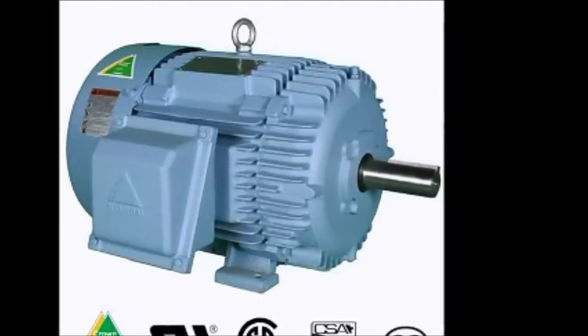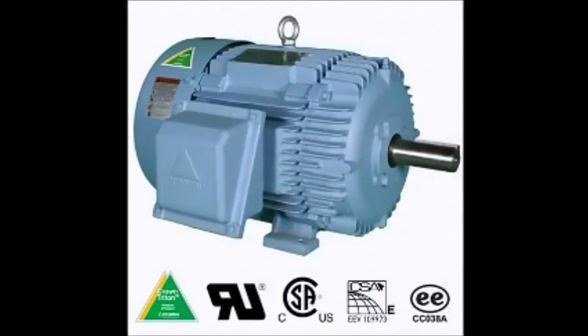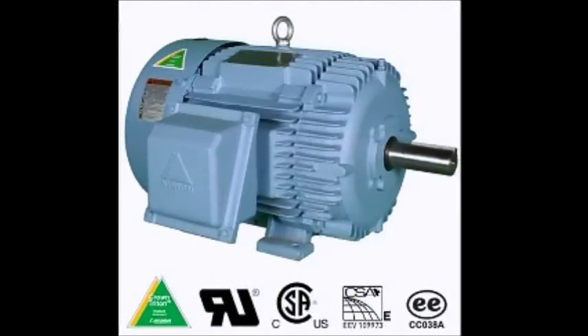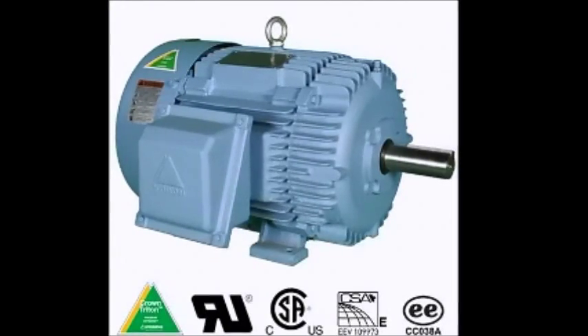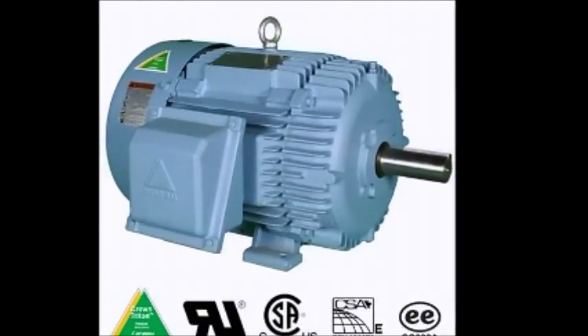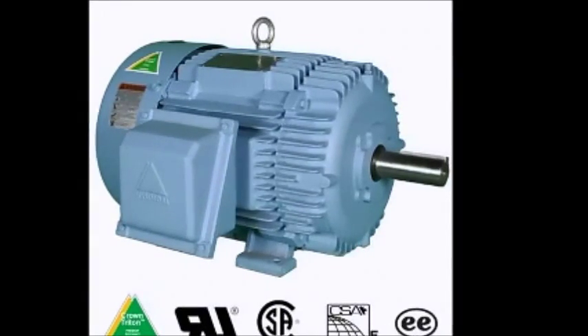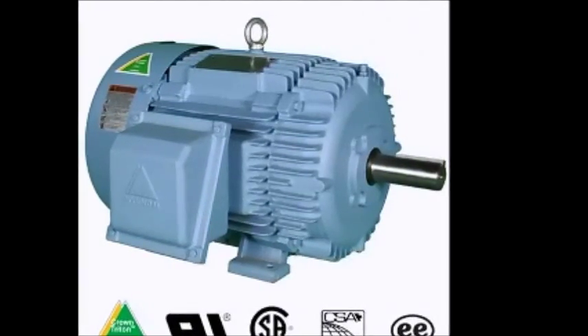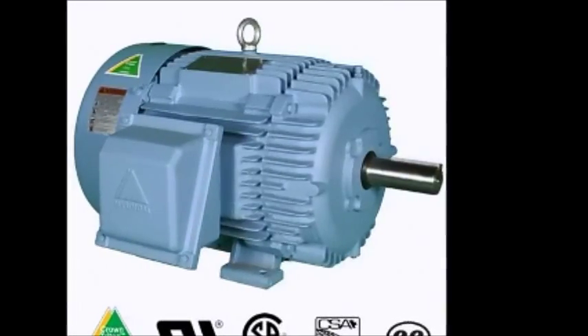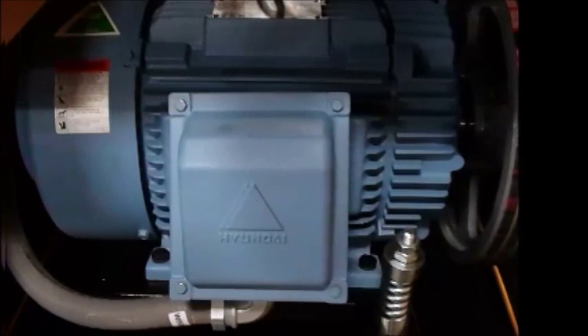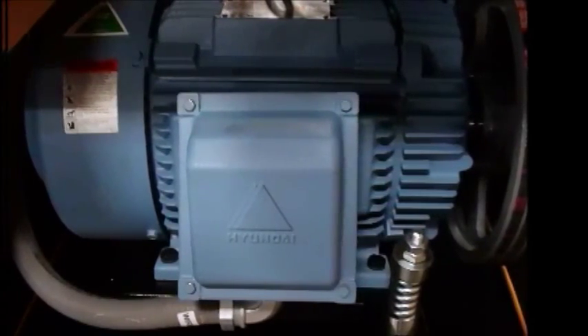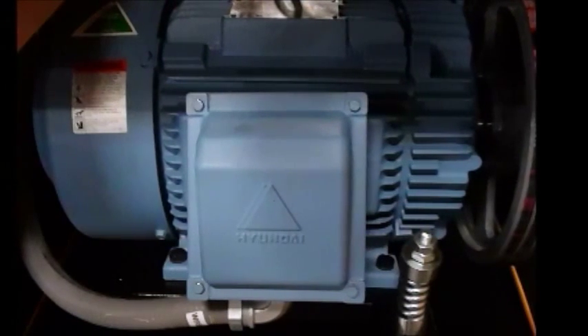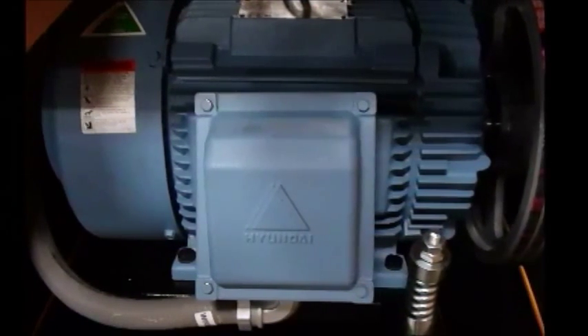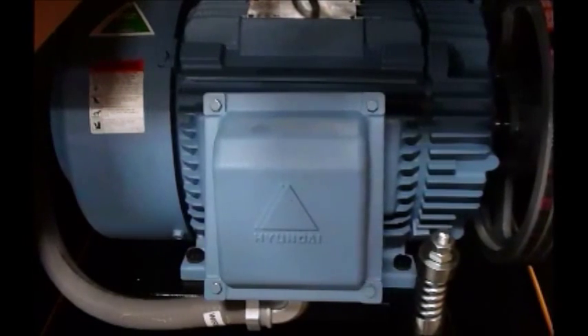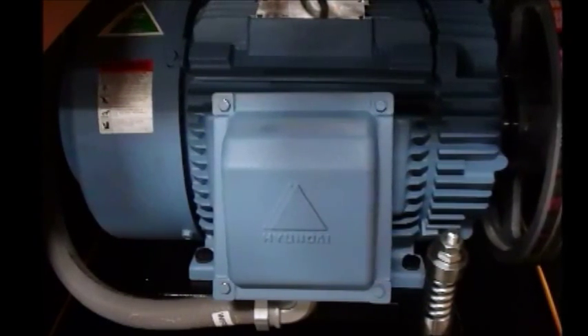TEFC enclosure, or totally enclosed fan-cooled enclosure, makes the motor internal components dust-free and waterproof. Dual-rated service factor, 1.15 for 40 degrees Celsius or up to 104 degrees Fahrenheit, and 1.0 service factor for 65 degrees Celsius or up to 149 degrees Fahrenheit.